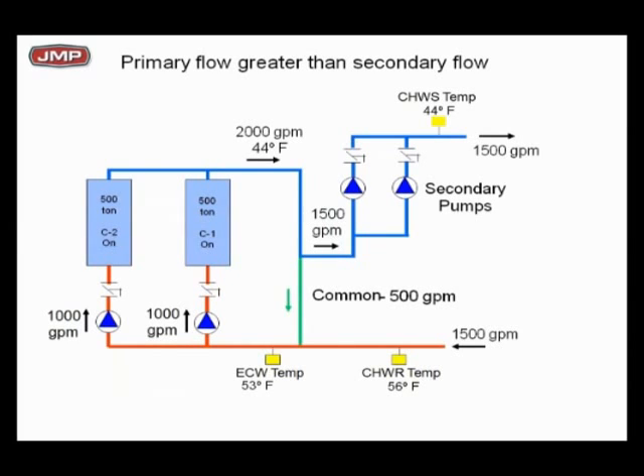Now you see what you've learned. You see how important it is to get all this together. So each chiller now has 53 degree return water, 44 supply, two chillers running. Everybody's still happy. Everybody's working fine. And this is a mode with chillers running all the time with primary and secondary. So each chiller is 75% loaded.